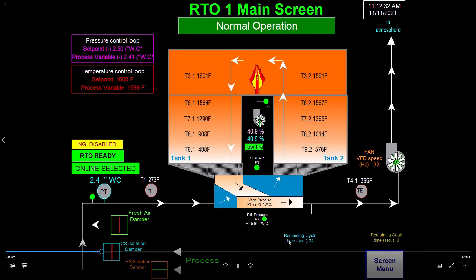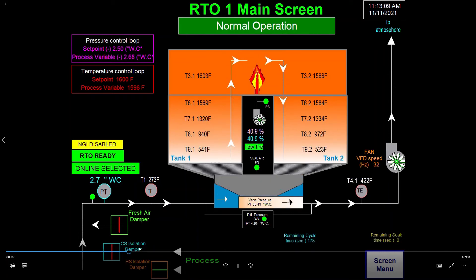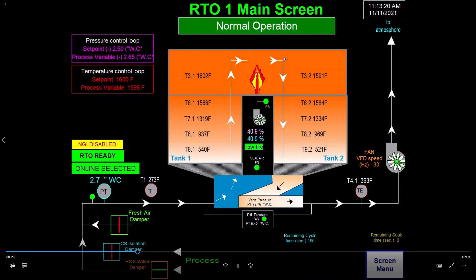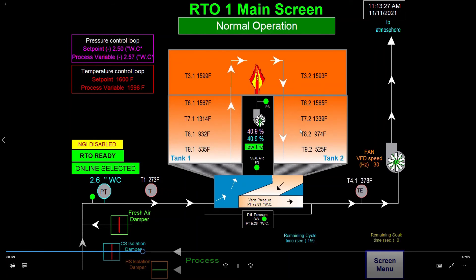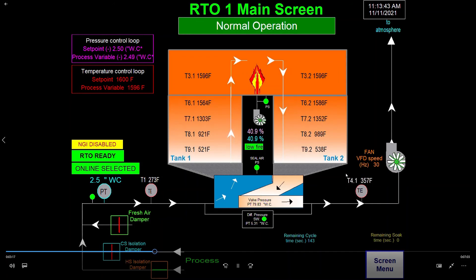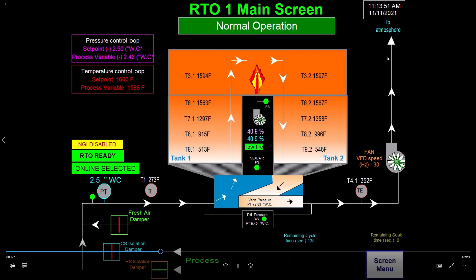This is the cycle time that tells us how long before the valve will switch. We're coming up on 30 seconds. I'm going to accelerate it here to show you the change in flow direction that's going to happen. It just changed — the valve is going to switch. Now the flow is going to go up through this bed, pick up heat in this bed that was heated in the previous cycle. That air will be brought to 1600 degrees Fahrenheit by the burner to destroy the VOCs. Then that hot, clean air will pass into this second bed that was cooled in the previous cycle to then heat it. As the air passes through, it will give off heat to this bed and cool the air so that it leaves the exhaust around 360 degrees — ranging from 360 to 425 at this thermocouple as it exits out clean through the fan. Now that's the principle of an RTO.